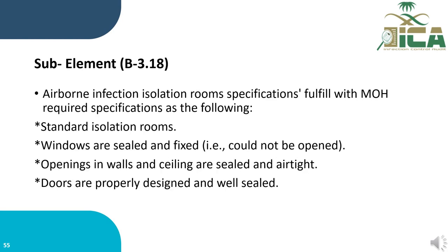Sub-element B3.18: airborne infection isolation room specification fulfilled with the MOH required specification as follows: standard isolation rooms, windows are sealed and fixed, openings in the walls and ceiling are sealed and airtight, and doors are properly designed and sealed. For this, we need observation.